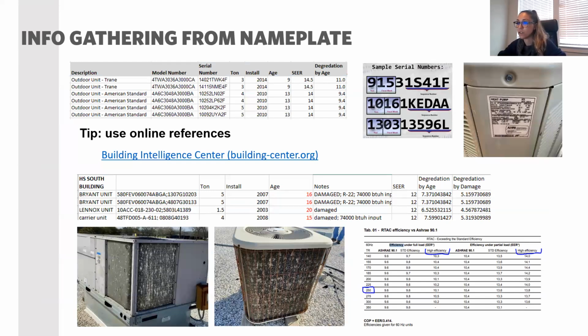This is what I was talking about. So many retrofits have happened in some of these buildings, so we try to gather this nameplate information, especially to be able to capture the age and the capacity. The model number and serial number are really critical for us. But even when you collect that, deciphering this information is still really hard, and we have to use some online references to figure it out, because eventually this information will affect the operation of the unit. And as I mentioned, in terms of information collection, the site visit is important, but capturing the existing condition of the equipment is also very critical.